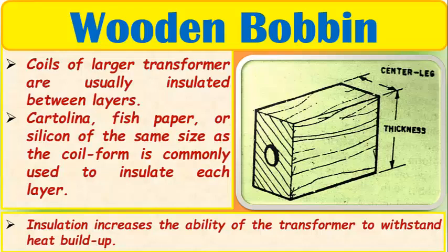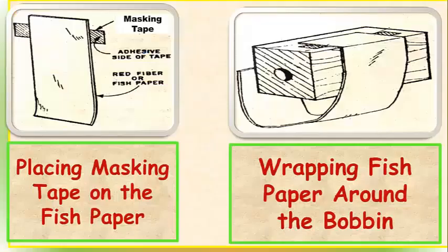The coils of larger transformers are usually insulated between layers. We can use either cartolina, fish paper, or silicone of the same size as the coil form to insulate its layers. The insulation increases the ability of the transformer to withstand heat buildup.